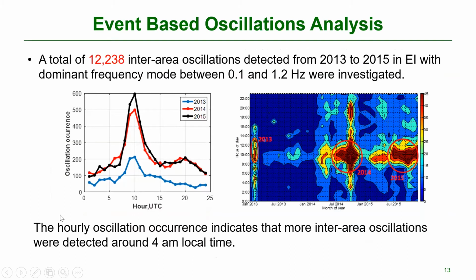If you look at this page, it says a total of 12,000 oscillations were detected in our case between 2013 and 2015 in the Eastern Interconnection, for this large inter-area mode. So you do have a lot of those happening. We're talking about a grid with very few renewables. What would happen if there's a tremendous amount of renewables and the magnitude goes up, and you really have to have a quick way to find out the source.